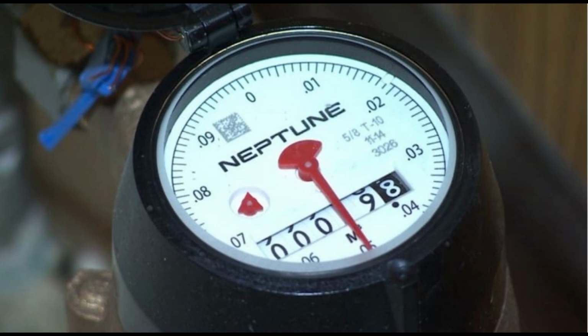Ultrasonic water meters use one or more ultrasonic transducers to send ultrasonic sound waves through the fluid to determine the velocity of the water. Since the cross-sectional area of the meter body is a fixed and known value, when the velocity of water is detected, the volume of water passing through the meter can be calculated with very high accuracy. Because water density changes with temperature, most ultrasonic water meters also measure the water temperature as a component of the volume calculation. There are two primary ultrasonic measurement technologies used in water metering. Doppler effect meters, which utilize the Doppler effect to determine the velocity of water passing through the meter.